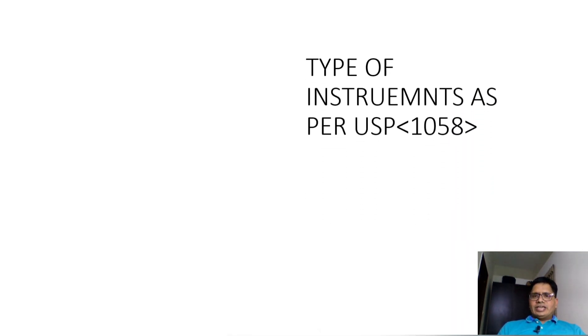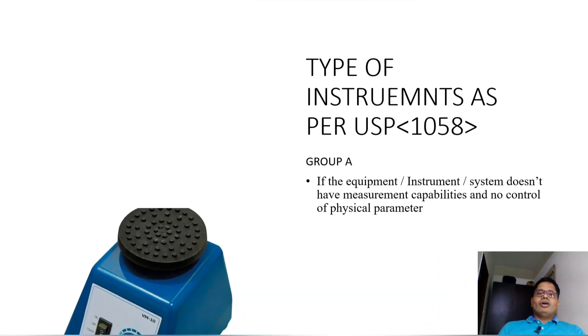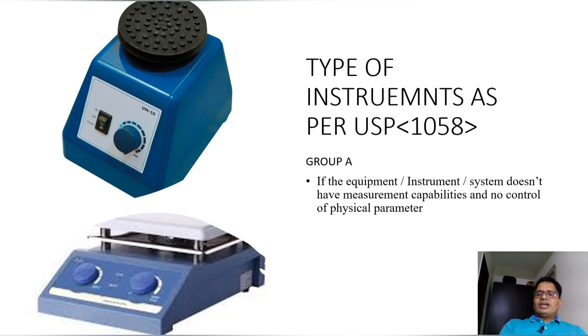As per USP 1058, there are Group A, Group B, and Group C instruments. Group A instruments are equipment or instrument systems that don't have measurement capabilities and no control of physical parameters. No measurement capability means no data is generated, no analytical analysis is performed, and they cannot control physical parameters like temperature, humidity, or any other physical parameter. Examples I have given are a vortex — no physical parameter is controlled, no data is generated — and a hot plate.